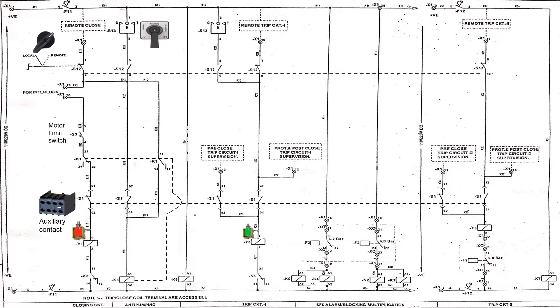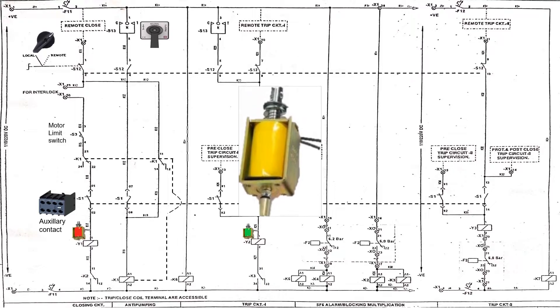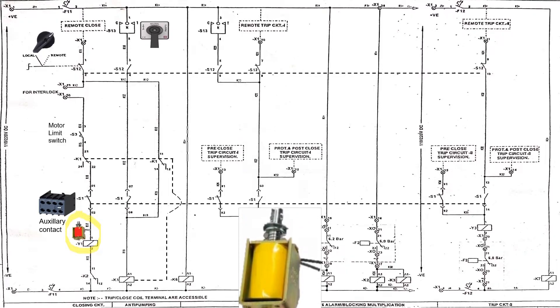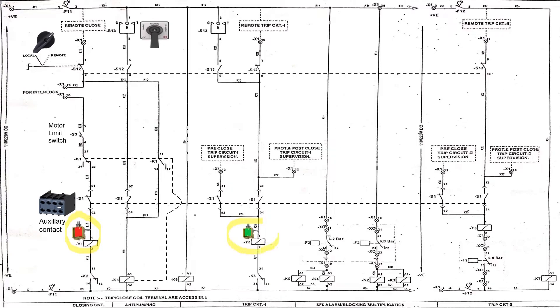Next is the coil, used as a tripping coil and a closing coil. The closing coil is shown in red and the tripping coil in green for understanding purposes. When the closing circuit is completed, the closing coil gets energized and closes the circuit breaker. Similarly, when the tripping circuit is completed, the tripping coil gets energized and the circuit breaker gets tripped.